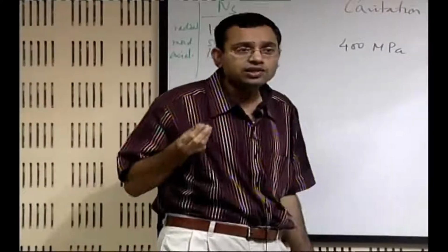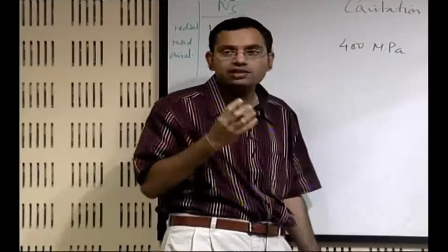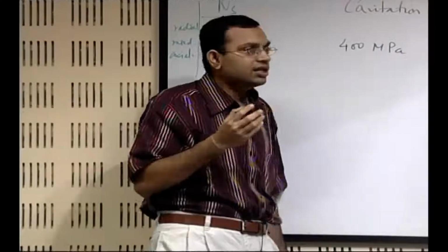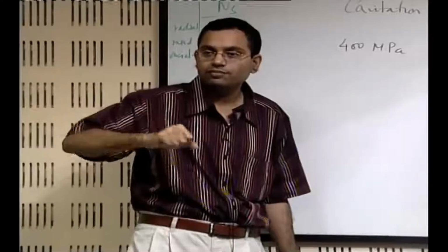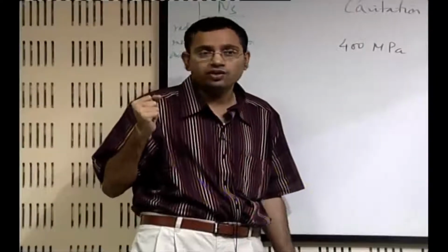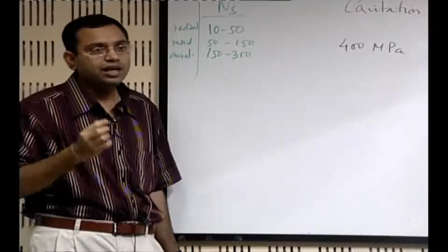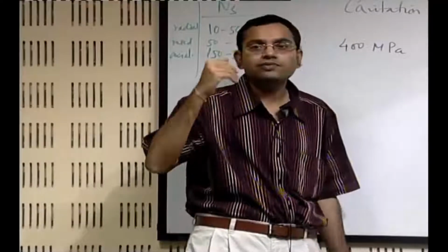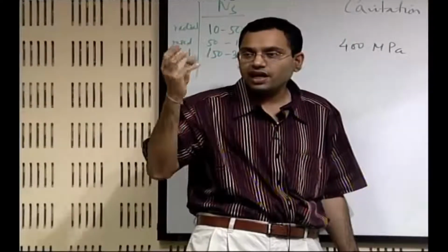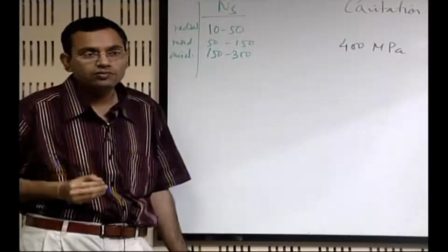There is a lot of noise also, and if this phenomenon is very serious, the noise is as if gravels are passing through the fluid. It is such a high noise, and the noise may be of varying frequency. Typically, small size bubbles will be associated with high frequency noise, and large size bubbles will be associated with lower frequency noise.